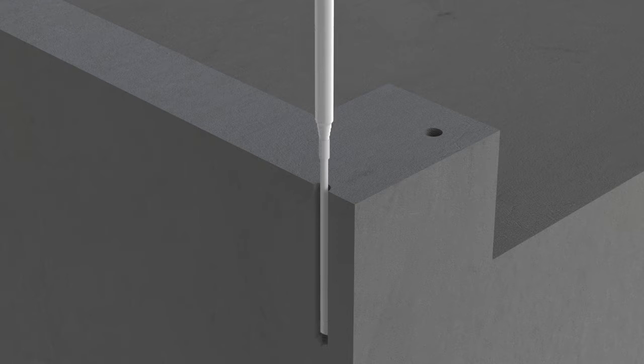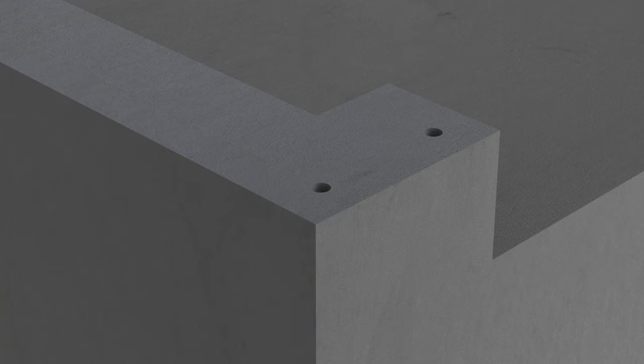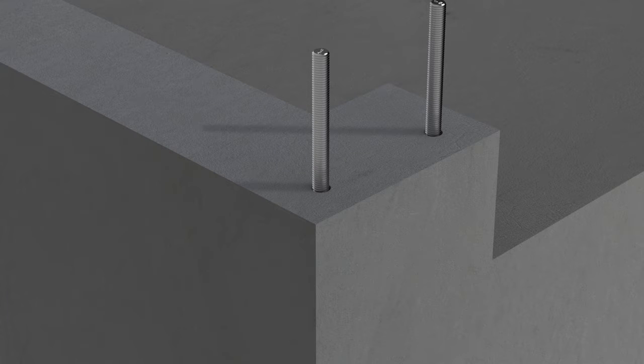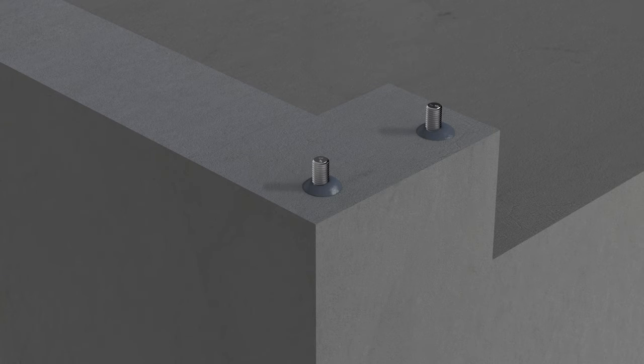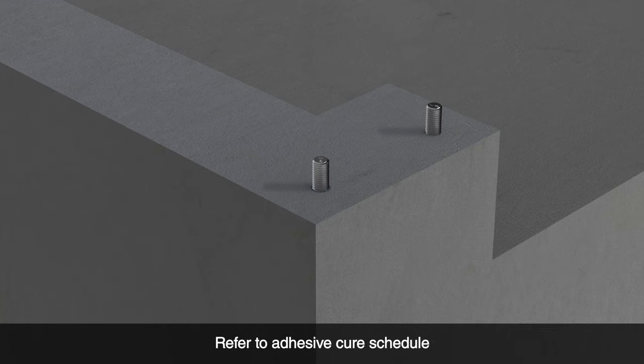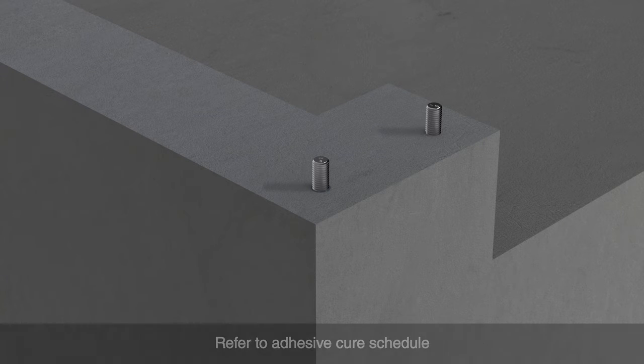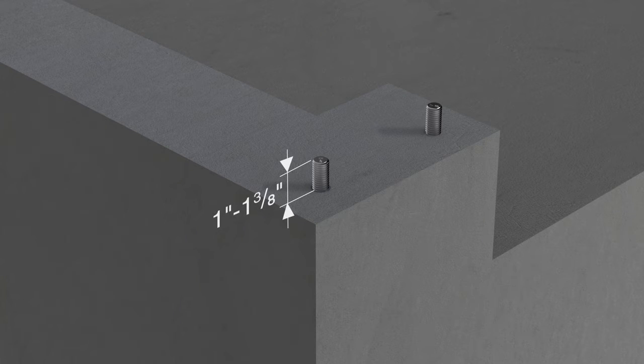To apply adhesive, place the nozzle at the bottom of the hole. Withdraw the nozzle slowly to prevent air pockets. Fill the hole 1/2 to 2/3 full. Insert a clean, oil-free anchor, turning slowly until the anchor is at the specified depth. Remove excess adhesive around the anchor. Do not disturb the anchor until it is fully cured. Note that the anchor should protrude above the concrete 1 inch to 1 3/8 inches.